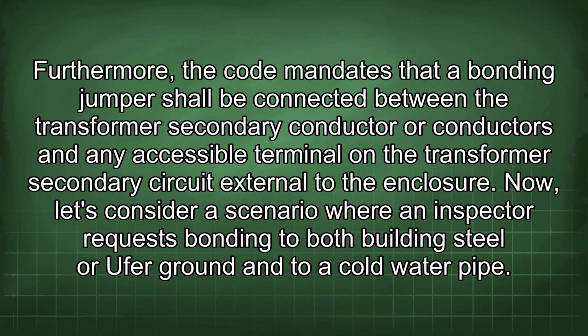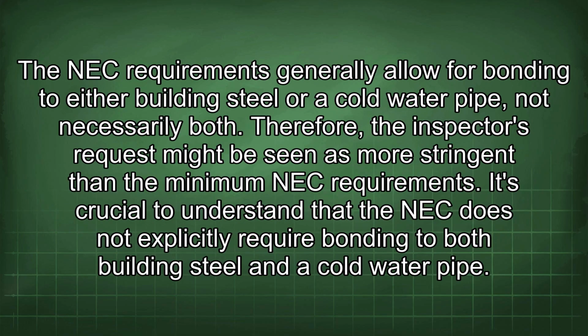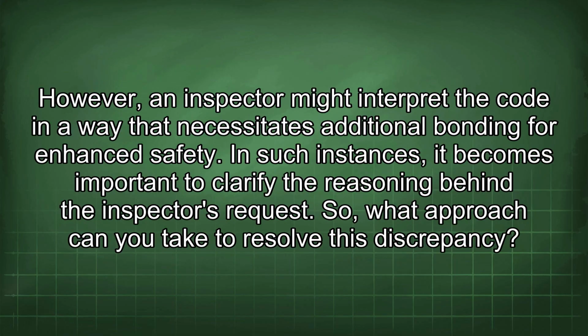Now, let's consider a scenario where an inspector requests bonding to both building steel or UFER ground and a cold water pipe. The NEC requirements generally allow for bonding to either building steel or a cold water pipe, not necessarily both. Therefore, the inspector's request might be seen as more stringent than the minimum NEC requirements. It's crucial to understand that the NEC does not explicitly require bonding to both building steel and a cold water pipe. However, an inspector might interpret the code in a way that necessitates additional bonding for enhanced safety. In such instances, it becomes important to clarify the reasoning behind the inspector's request.